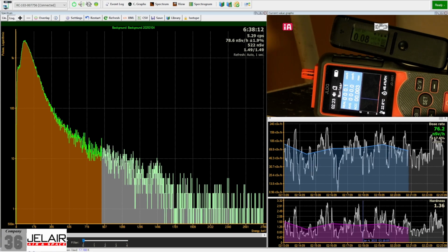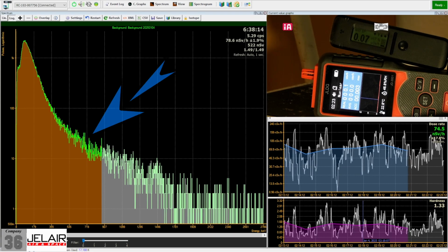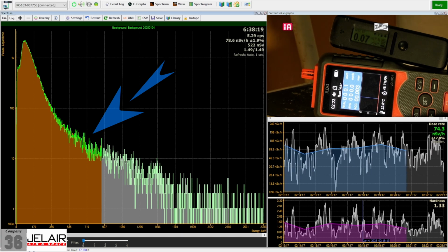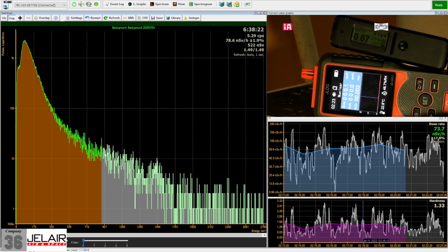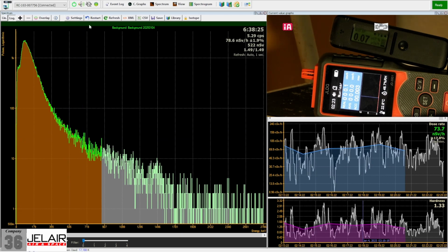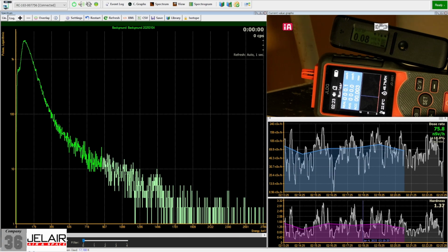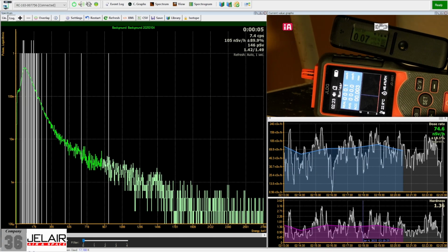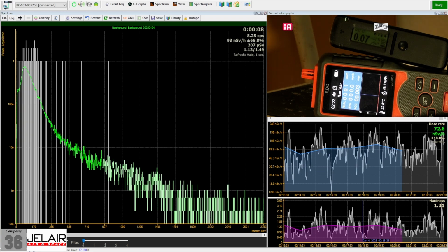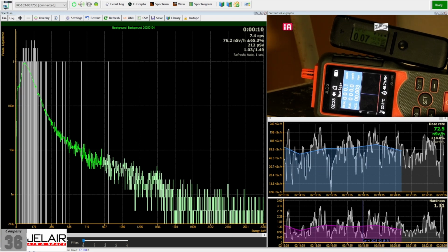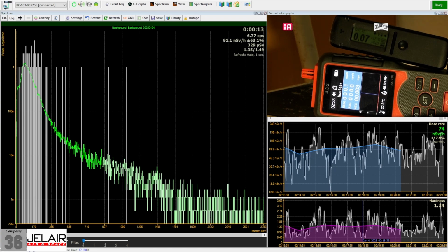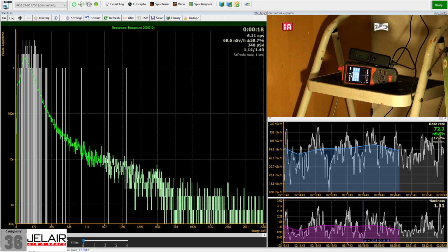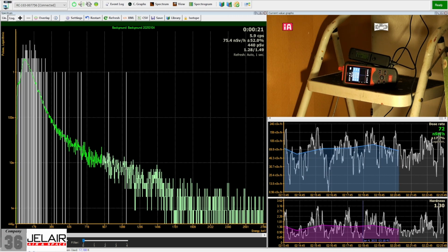So the green line you see on the left image is the recorded background spectrum, the baseline spectrum. I'm now gonna reset the spectrum grab. I did it there. Now the gray lines that emerge is the spectrum as it is being grabbed live by the Radiacode. So if I didn't change anything, right now it's not recording anything but the background radiation, it will become like the green line again.